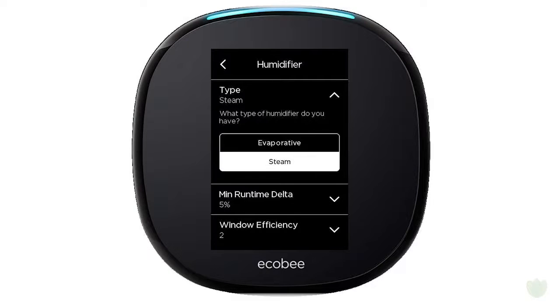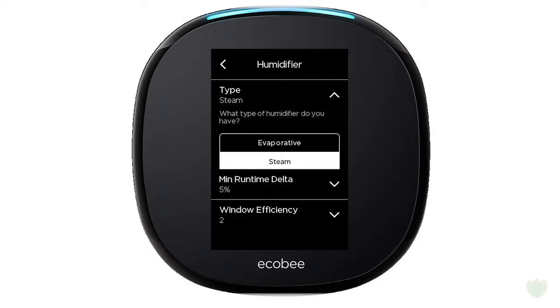If you go ahead and switch it over to steam, doesn't matter if you have an evaporative humidifier or a steam humidifier. The only difference in the settings is that you will be able to continue running that humidifier whether or not there's a heat call. So that humidifier and the fan is going to kick on. It's going to maintain that humidity set point. It's not going to matter if the furnace is running or if there's a call for heat, right? So we always kind of recommend you use steam.